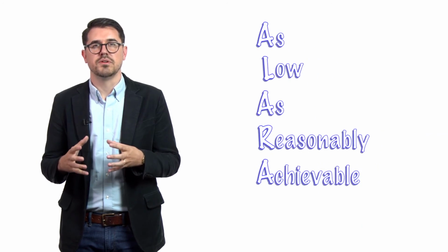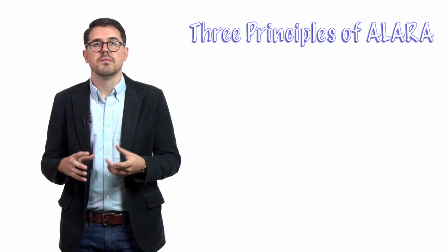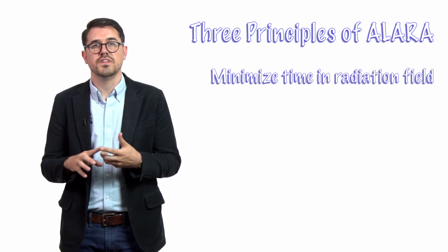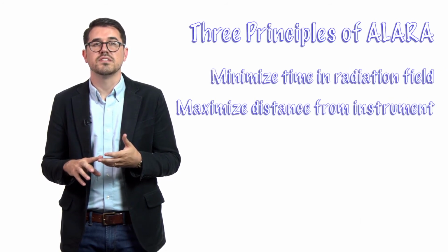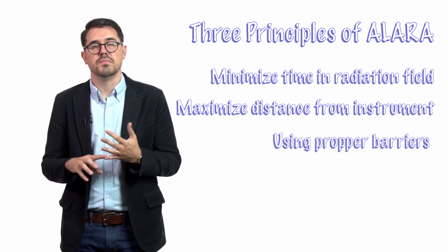In radiation safety, there's a common acronym, ALARA, meaning as low as reasonably achievable. We strive for this standard by following three principles: minimizing time spent in the radiation field, maximizing our distance away from the instrument, and using the proper barrier to shield the beam.